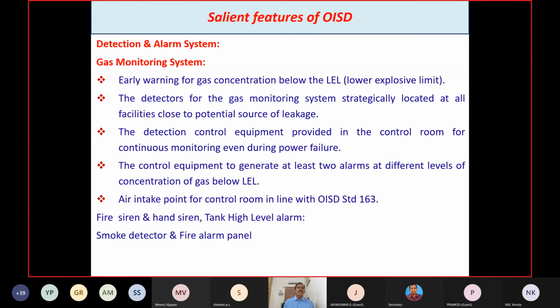And the detection and alarm system, that is the gas monitoring system, for early warning of gas concentrations below the LEL, lower explosive limit. The detectors for the gas monitoring system should be strategically located at all facilities close to potential sources of leak. The detection control equipment is provided in the control room for continuous monitoring even during power failure, so UPS supply should be given.